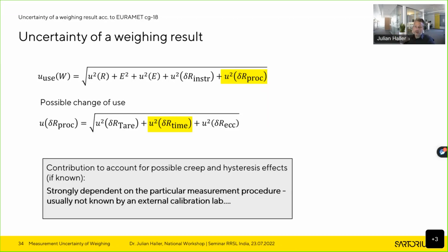So what I recommend, to get at least some impression of how big hysteresis is for my application, is to make respective measurements or estimations. For example, what you can easily do, if you do a long-term measurement, is afterwards just check the zero return. If you have a hysteresis effect, the balance will not come back to zero exactly after 1 hour of measuring or whatever. If you have a non-significant effect, it should roughly come back to zero. So you can estimate how big this effect is for your particular application. That is what I would generally recommend.